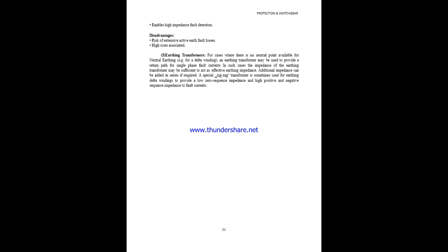Next is the earthing transformer. For cases where there is no neutral point available for neutral earthing, an earthing transformer may be used to provide a return path for single phase fault currents. In such cases, the impedance of the earthing transformer may be sufficient to act as an effective earthing impedance. Additional impedance can also be added in series if required. A special zigzag transformer is sometimes used for earthing the delta windings to provide low zero sequence impedance and high positive and negative sequence impedance to the fault currents.